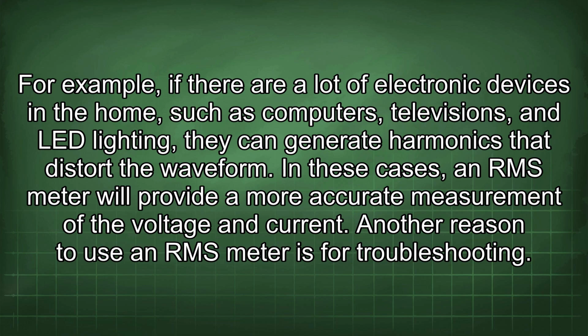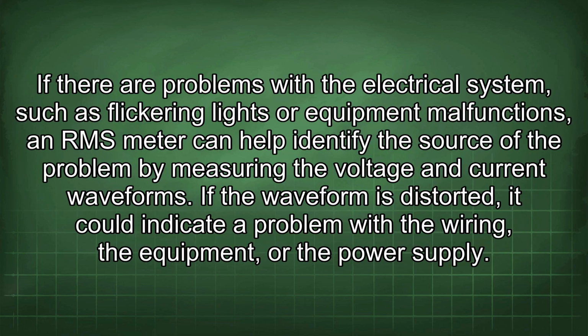Another reason to use an RMS meter is for troubleshooting. If there are problems with the electrical system, such as flickering lights or equipment malfunctions, an RMS meter can help identify the source of the problem by measuring the voltage and current waveforms. If the waveform is distorted, it could indicate a problem with the wiring, the equipment, or the power supply.